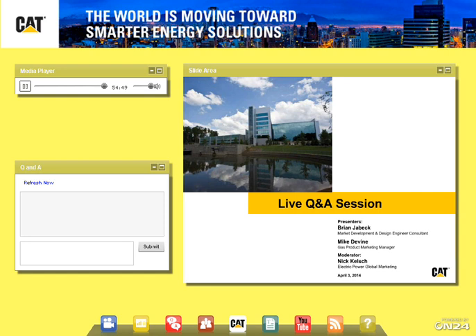Yes, Adam, that's a very good question. The EPA does require the reporting, tied to a non-resettable hour meter, of how you operate, why you operated, and when that operation occurred, and you have to be able to prove that. The challenge is that you are providing all that information to your local air board. So I've seen some templates, but they do vary. I would say that you have to talk to your local AHJ, your local air board, and find out if they have a firm process or procedure that they want followed and how they want that documented, because it does vary across North America.